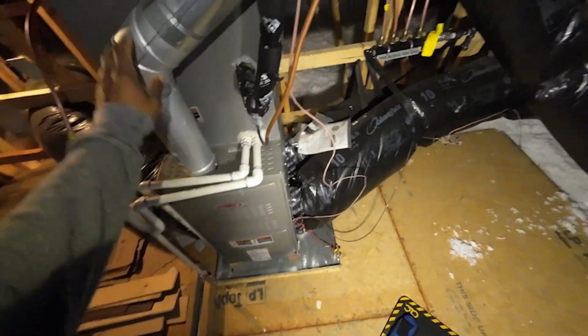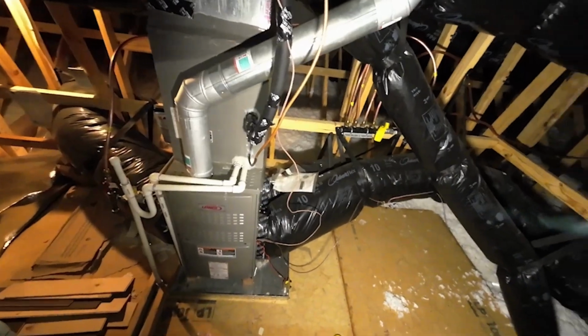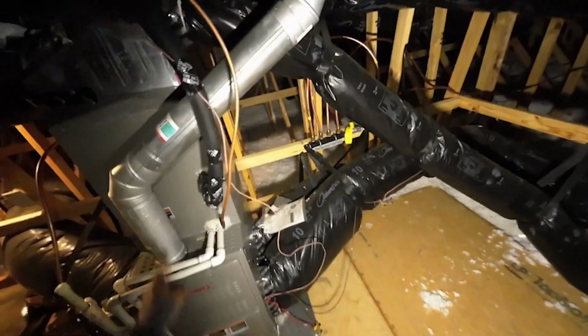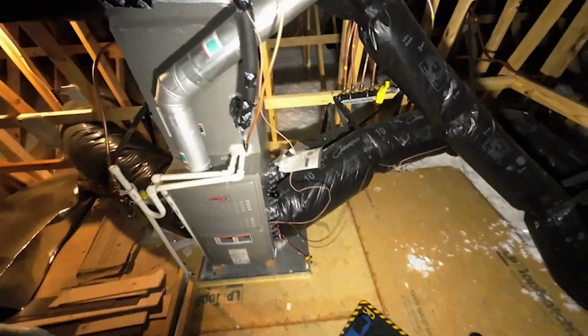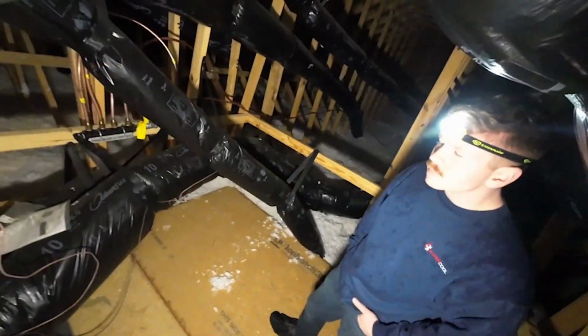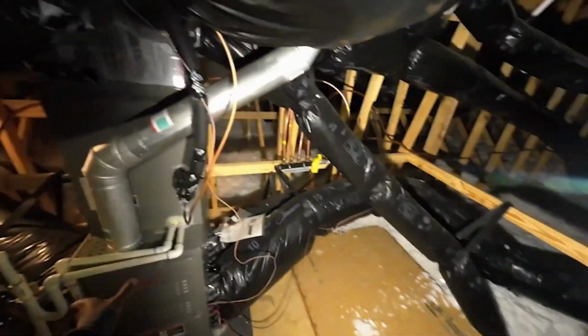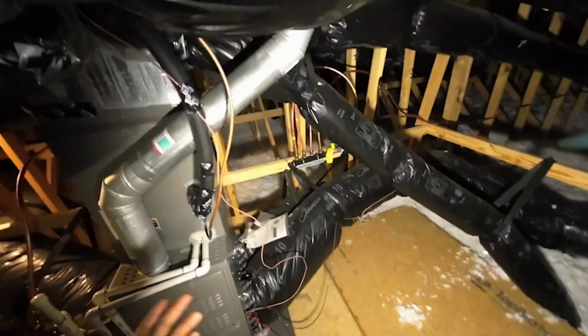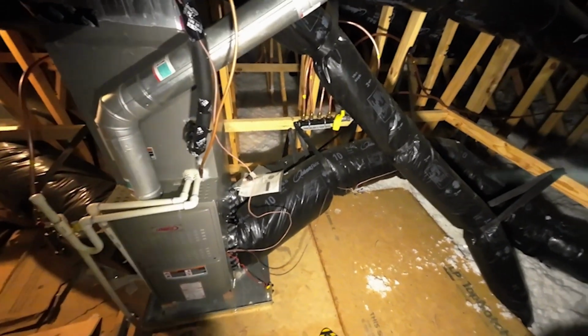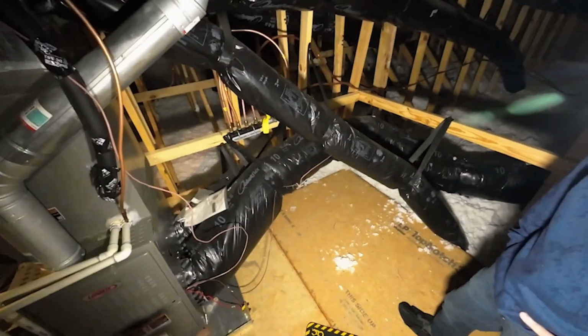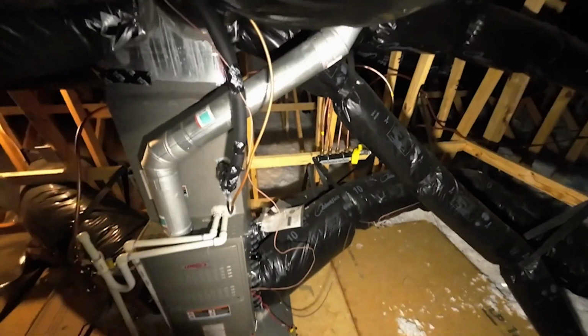Alright, cool. So these are what you call an 80% gas furnace. You can tell the difference between 80% and 90% just based off the flue pipe as a first indication. See, that's going to be the galvanized metal there. They call that B vent. A 90% furnace is going to have plastic, like a white PVC coming out of it. The reason is that the exhaust gases are not as hot as they exit the furnace, just because it's pulling that much more heat energy out of it.